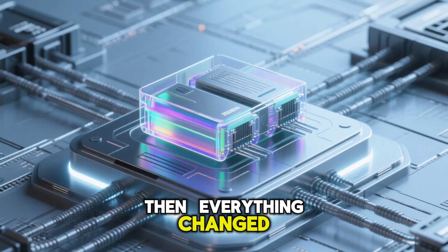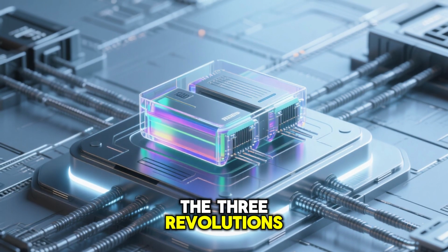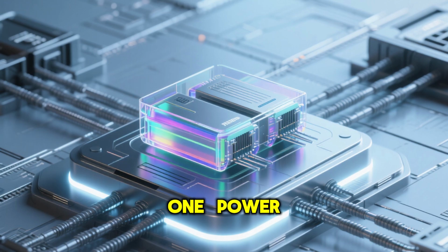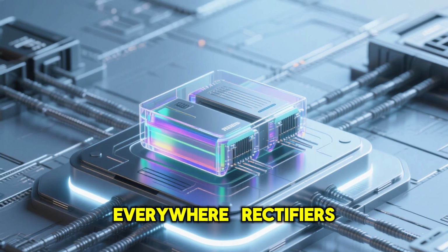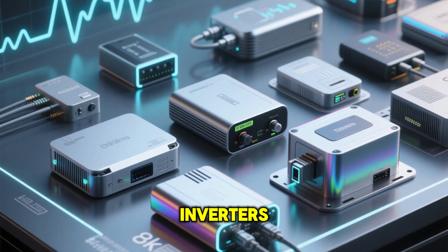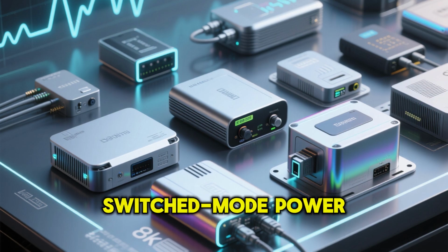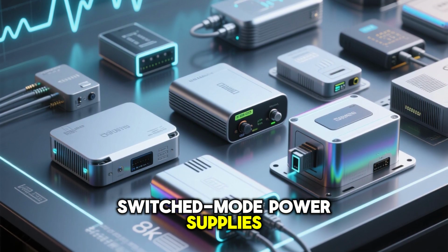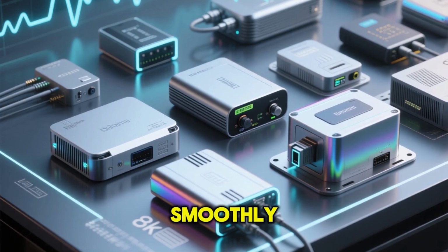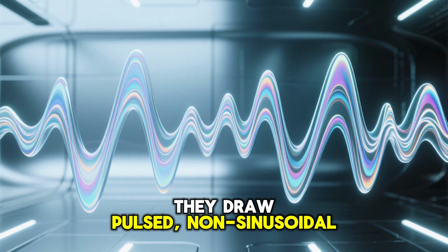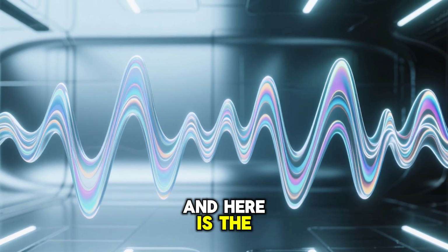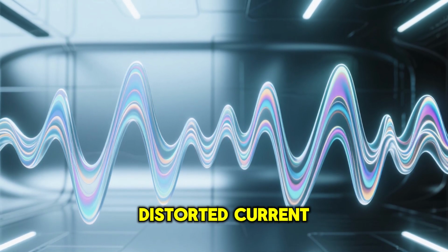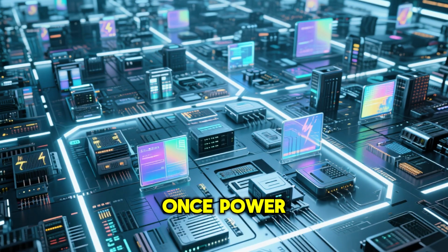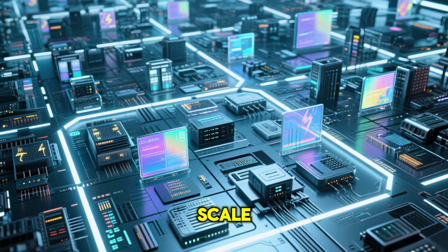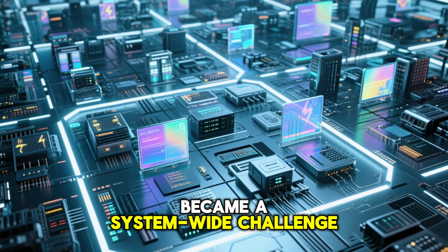Then, everything changed. The three revolutions that changed everything. 1. Power electronics everywhere. Rectifiers, inverters, variable speed drives, switched mode power supplies. These devices do not draw current smoothly. They draw pulsed, non-sinusoidal current. And here is the key point. Distorted current creates distorted voltage. Once power electronics entered the grid at scale, voltage quality became a system-wide challenge.